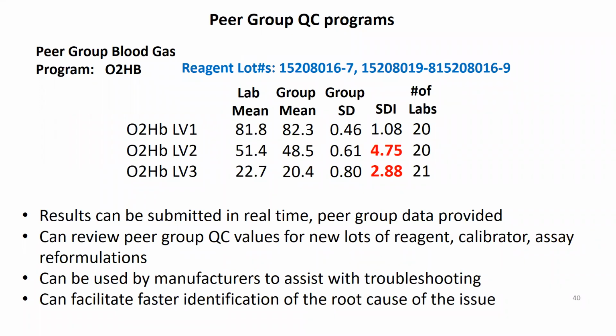So through the use of peer group QC programs, results can be submitted in real time, allowing the lab to compare its results to the peer group. Using the data, the lab can also evaluate QC values for new lots of reagent or new lots of calibrator by comparing their values to those obtained by the peer group for that specific lot. The data can also be used by manufacturers to assist labs with troubleshooting. So in these ways, participation in peer group QC can lead to faster detection of analytical measurement system issues, identification of the root cause of issues, and faster recovery from the out of control event.